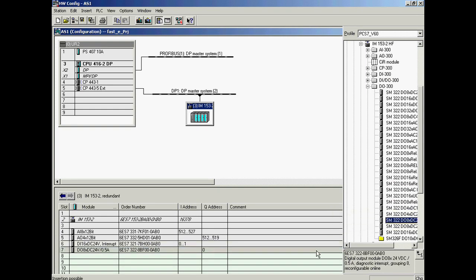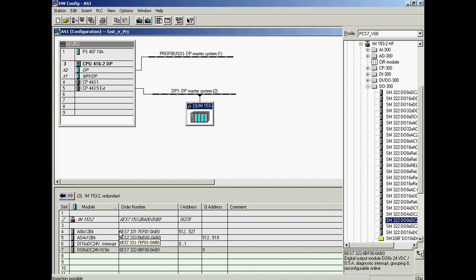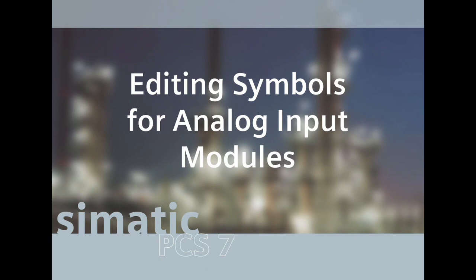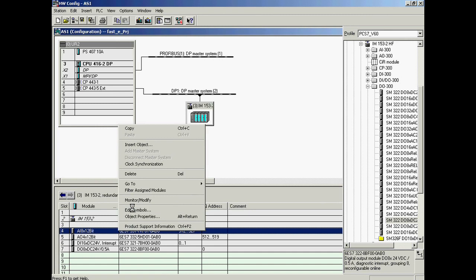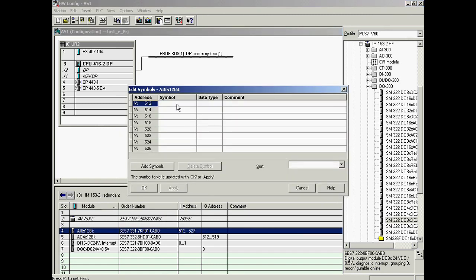In the hardware configuration, the IM153-2 interface for the ET200M distributed I/O system was inserted and communication was set up. To use symbolic addressing of I/O throughout the configuration — instead of rack, slot, channel numbers, or memory locations — each address is given a unique symbolic name and comment in the Edit Symbols dialog. The symbol name 'PV in of controller 1' is entered in the first line as well as in the comment column, by copying the symbol name to the clipboard and pasting it into the comment field.